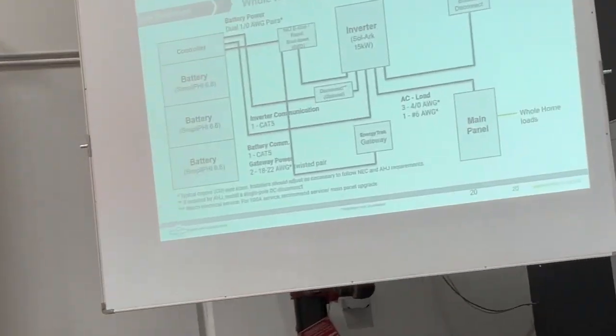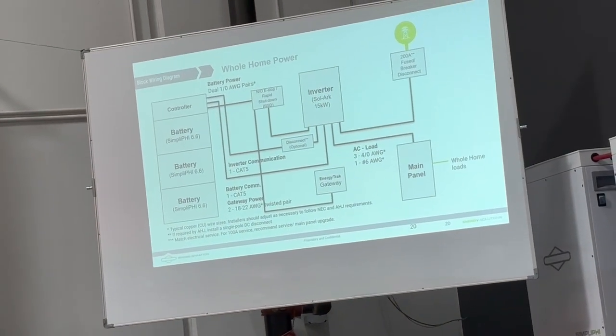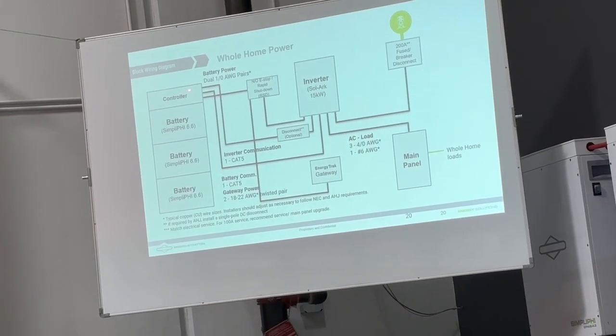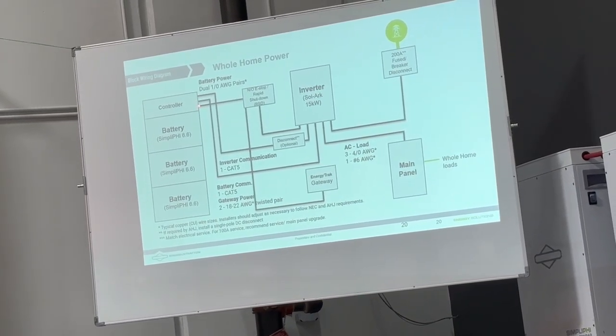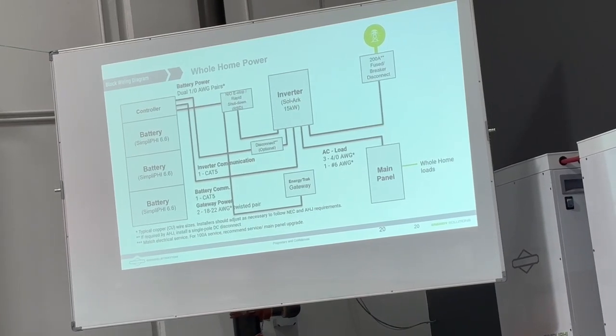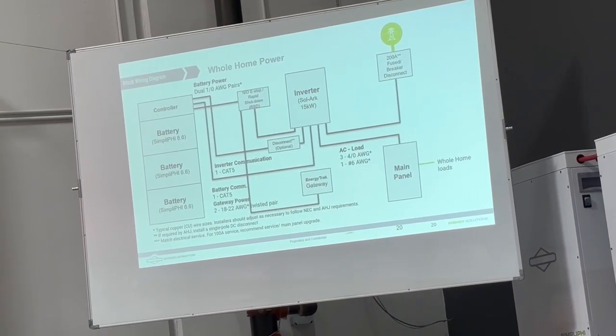Okay, and here we're looking at coming out of the controller. Now for a 15K, because they've got dual sets of inputs there, we're recommending coming out of the controller with two 1-aught sets. So you'd have two reds, two blacks coming out, 1-aughts, or 2-aughts. We've actually, in this one here, put 2-aughts in there. We had it on hand, and those will go into the DC breakers on the Sol-Ark. Then out of the Sol-Ark, we're feeding our power to our main loads panel of the house. If you're using copper, this could be 3-aught instead of 4-aught. If you're using aluminum, that would be a 4-aught connection.